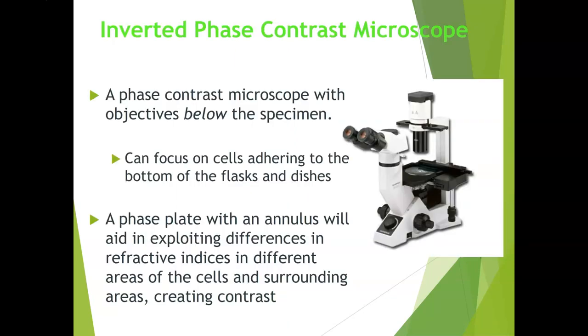Tissue culture facilities will almost always have the inverted phase contrast microscope in the facility. This is because this scope is able to visualize living cells adhered to the bottom of flasks and dishes. There is no need to kill or stain the cells, and the objective lenses are located below the stage in order to be able to focus on the bottom of tissue culture flasks and plates. The light will also pass through a phase plate which will improve the contrast of the specimen so that living cells can be seen. The next image will explain the way the phase plate works.